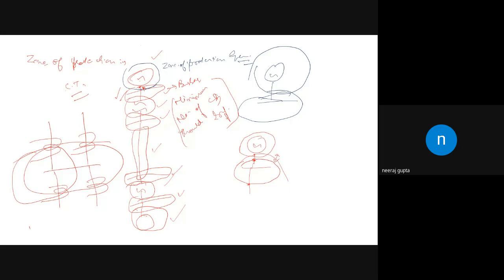So from this you will see how complex the protection system is, that we have to take into consideration all these factors, that is, overlapping zones contracting and expanding. So these things we have to take into consideration. It is a very complex system, and we have to take all these facts into consideration. Then whenever a fault occurs, the minimum number of circuit breakers would trip. Otherwise, there is a problem for the whole of the system.